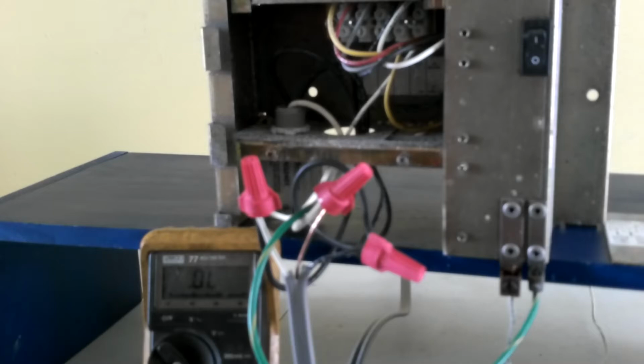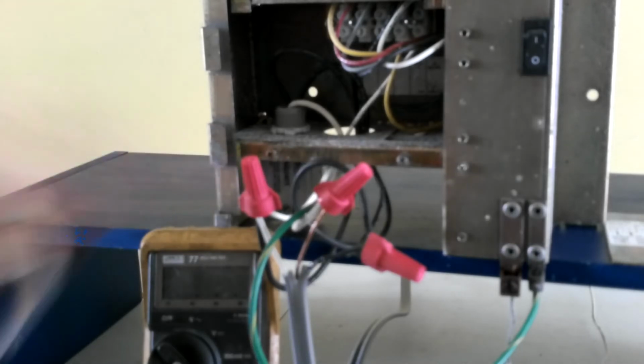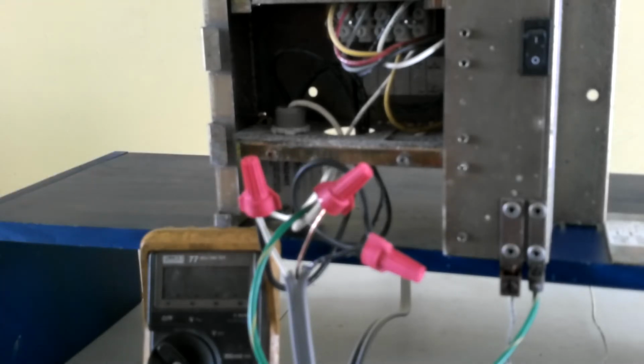When that happens, you'll know it when you open the pedestal. You'll have this smell of electrical burnt plastic. You'll also find in a lot of cases that the plastic cube on the surge arrestor has melted and gotten heat and burned a little bit. That indicates that it's pretty much bad and needs to be replaced.